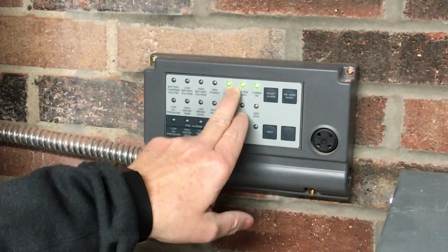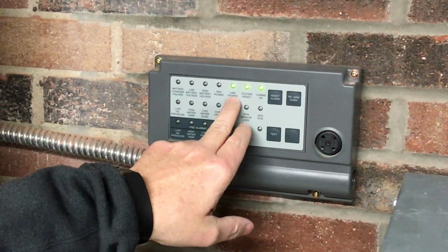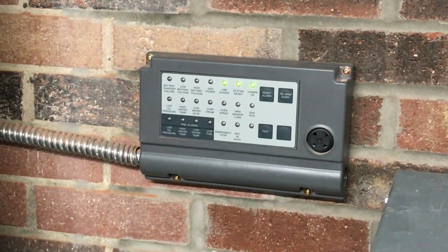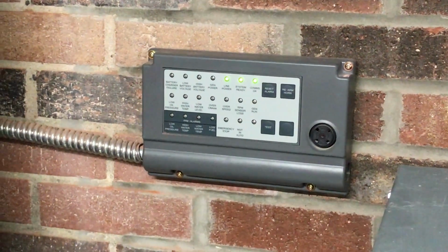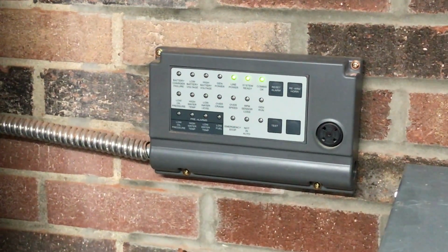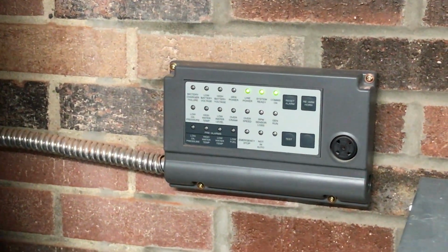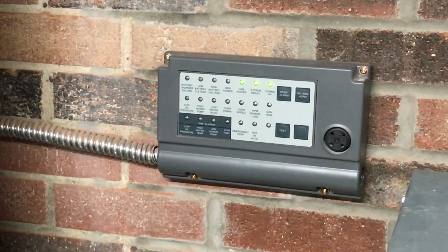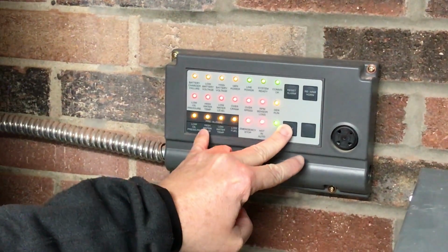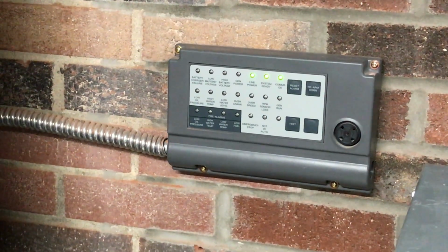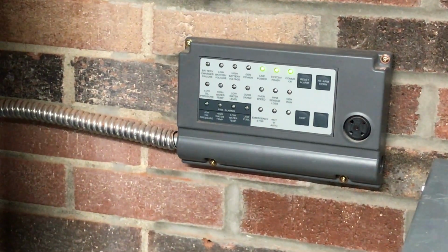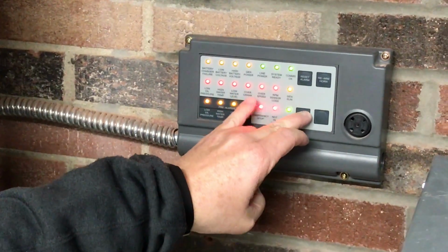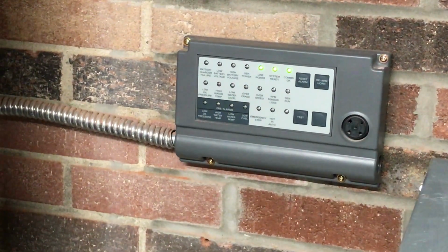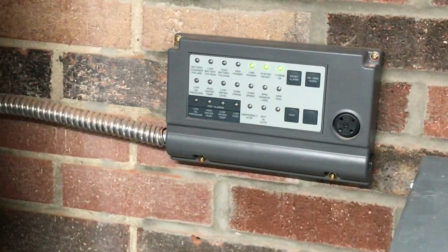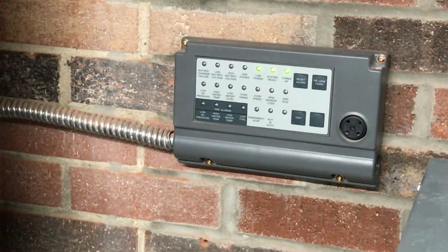In the event you come through here, this is just good status. 3 solid green lights, you're good to go, no issues. If the line power light is actually flashing, all that means is that you've had an event and the generator's transferred over and you ran on generator power for some time. So it's just a visual cue. All you have to do is hit reset and the alarms will go back to solid green. Those 3 alarms down here are just pre-alarms that say someone needs to come check me. It may get an event where I'm not going to be able to start. All these red ones are situations where the generator is locked out and it's not going to run. So it's definitely a situation that needs to be taken care of.